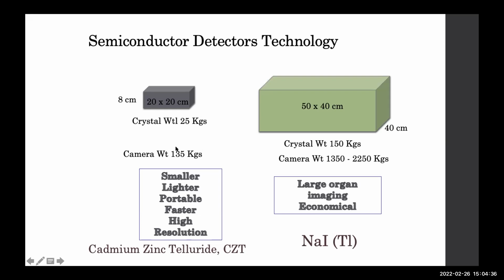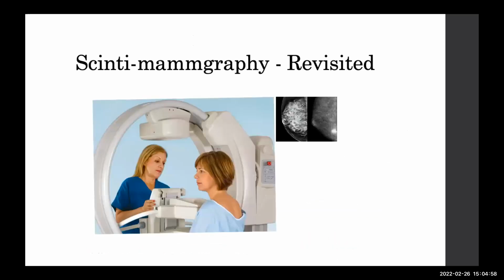and the total gamma camera becomes 135. And this solid state detector, the semiconductor detector, is made of cadmium zinc telluride. It is very costly, but it gives very fast image acquisition, sharp images and good energy resolution, and they are frequently used for specific organ imaging like breast or cardiac SPECT. You can see this is the breast gamma camera, where scintimammography is being done. It uses a solid state detector like the CZT crystal, which I have described.